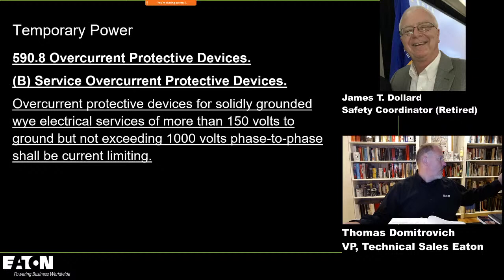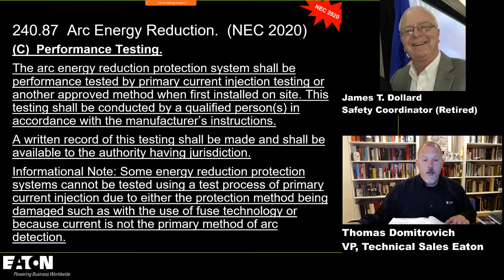And even if you're on that load side in temporary power, if you've got a 400 amp molded case circuit breaker that has been on 6 different jobs, exposed to wide-ranging environments and dampness, and maybe it saw a fault at or near its interrupting rating, we don't know what's going to happen there. But if we have current limiting requirements, we're going to have current limiting fuses or current limiting circuit breakers. And if it's current limiting fuses and they open and we replace them, where is our level of protection? Yeah. Right back where we started. Absolutely right. Yep. And you're getting pretty close.